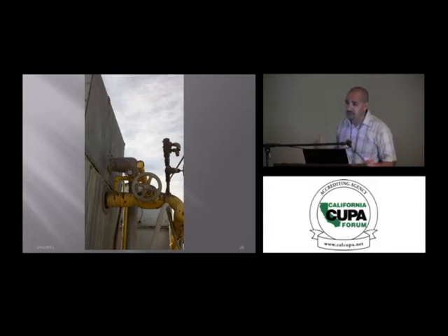This one is on the opposite side. The reason why is they ran out of room. From the face of the condenser to the wall, they had no room. On the other 2 condensers, there must have been probably about a foot of space, so they had room for the relief valves, but this is on the opposite side. And so once I made the recommendation and talked to the plant manager, he just said, wow, had no idea. Yeah, usually when you see relief valves plugged, it means they've been having a problem.